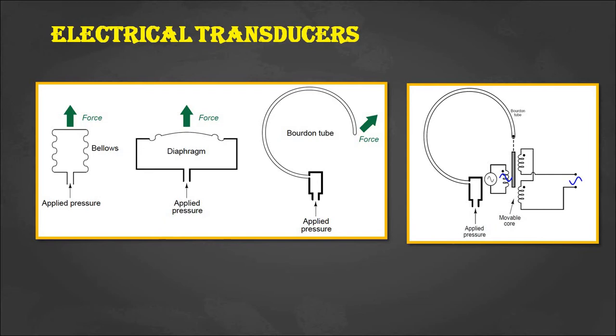Here is an example for the measurement of pressure, where two transducers are present. One is the Bourdon tube, which is the mechanical transducer. This Bourdon tube converts the applied pressure into a displacement. That displacement is then converted into voltage by using an electrical transducer — that is LVDT. Depending upon the core movement in LVDT, the output voltage will vary. The output voltage can be transferred over a long distance and the data can be stored, which is possible by converting the displacement into another quantity.